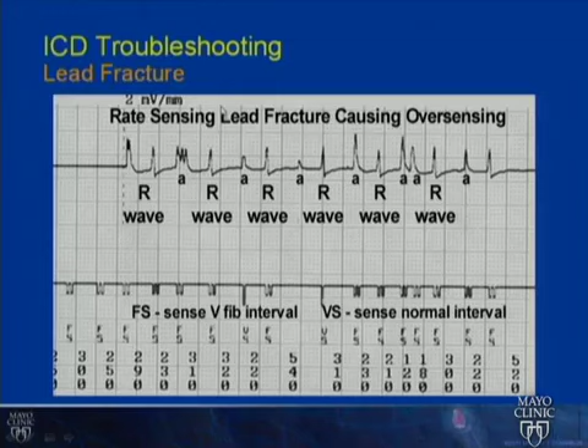And the defibrillator actually thought that these were tachyarrhythmias, because the defibrillator gave us the marker channel showing cycle lengths of 290, 230, 310 in the VF zone. As a result, if this sensing in the VF zone lasts long enough, the defibrillator would charge and discharge because of these noises. So recognizing that these signals are fairly large, discrete, and can be reproduced by physical maneuvers, that would be the diagnosis of lead fracture in this setting.